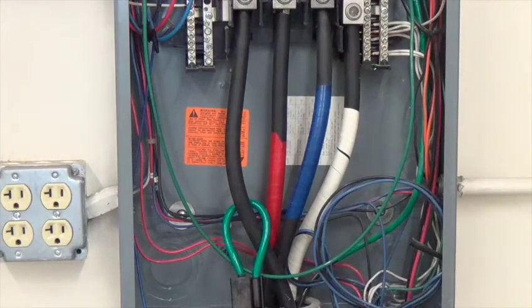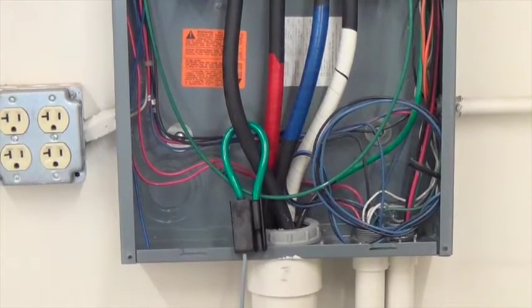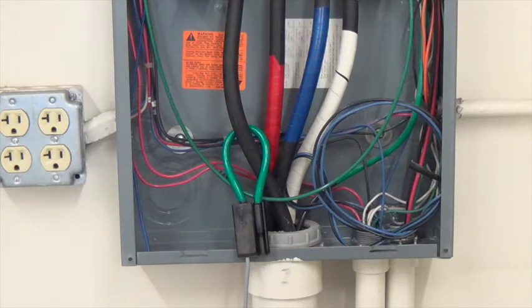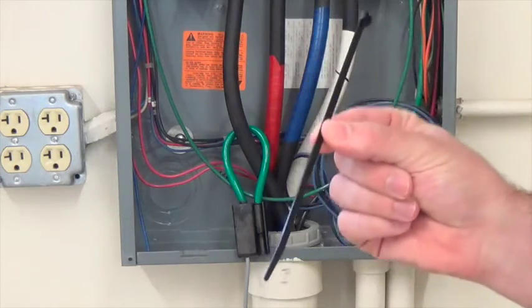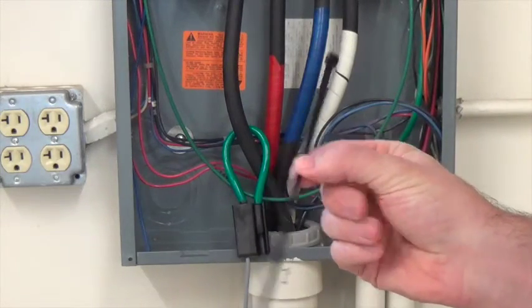As you can see, as the unit hangs, because of gravity it naturally sits in this position. That's good because Rogowski coils will have greater error as they get closer to the integrator. You can also take a zip tie and wrap that around it to further keep it in position.